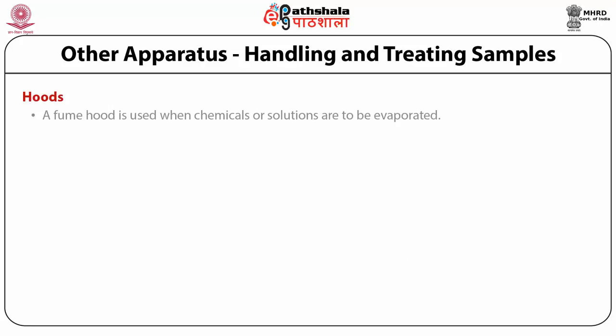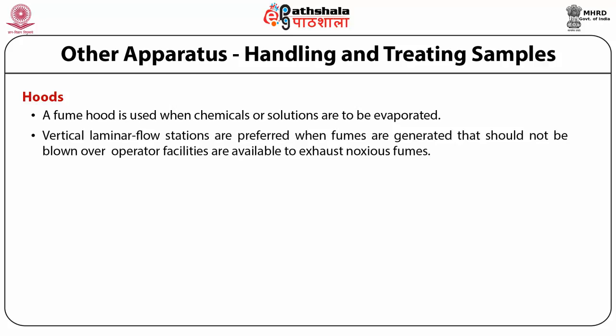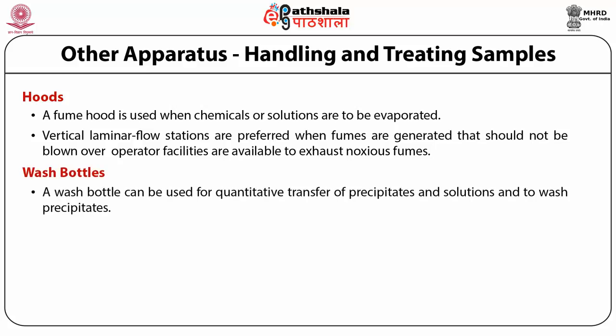A fume hood is used when chemicals or solutions are to be evaporated. When perchloric acid or acid solutions of perchlorate are to be evaporated, fumes should be collected or the evaporation carried out in fume hoods especially designed for perchloric acid work. Vertical laminar flow stations are preferred when fumes are generated that should not be blown over the operator. A wash bottle should be handy in any analytical laboratory, to be used for quantitative transfer of precipitates and solutions and to wash precipitates. These are commercially available in a variety of shapes and sizes.